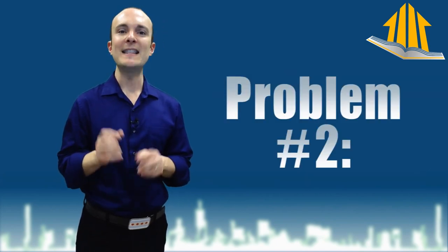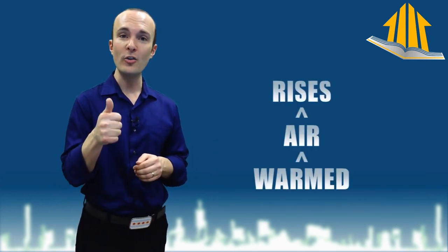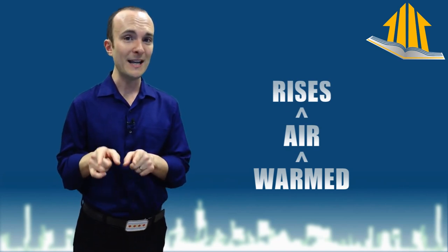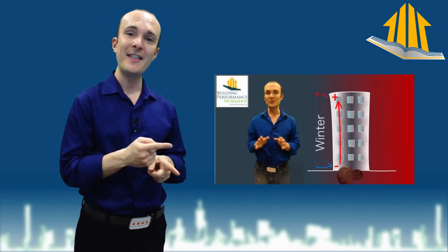Second problem is that the way air moves in heating season, which is most of my year in Chicago, all the air in the bottom of the building ends up going all the way up through the building. So if there are any air quality issues in a room like this, they're going to be a problem for everyone above. You can learn more about that by clicking on this video.